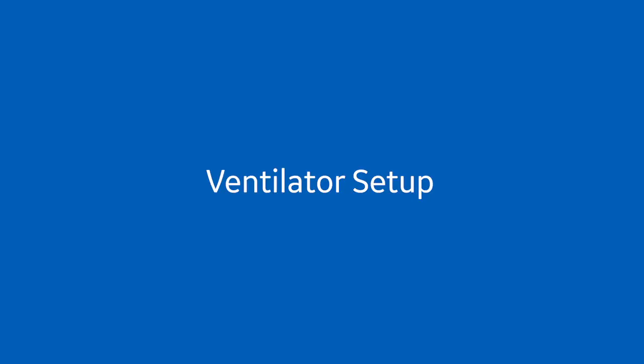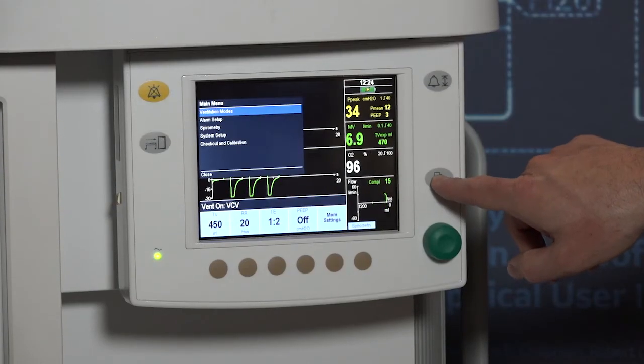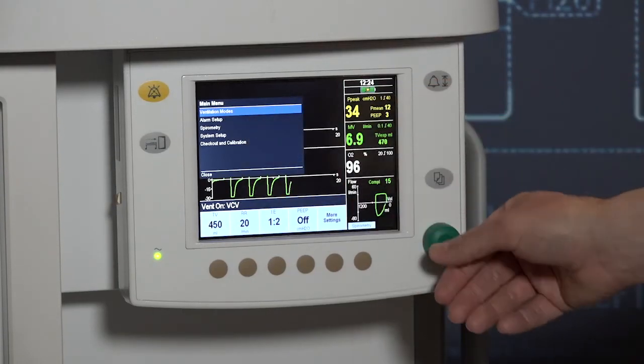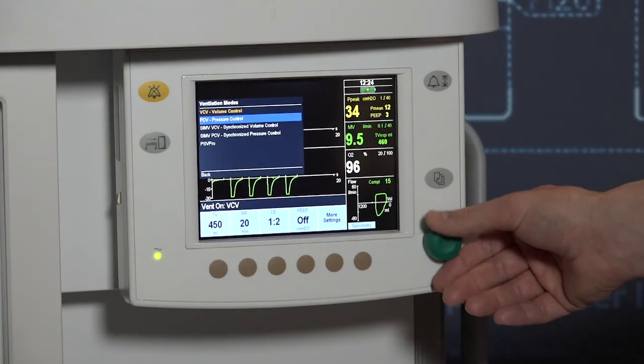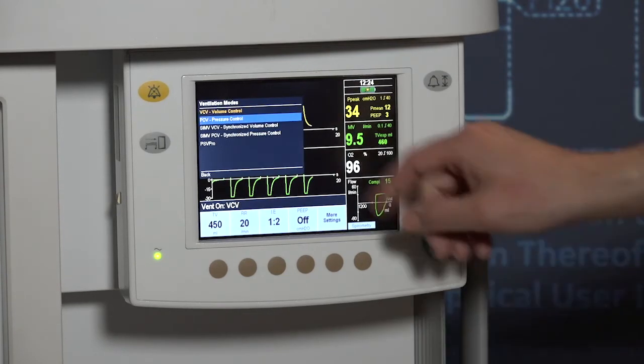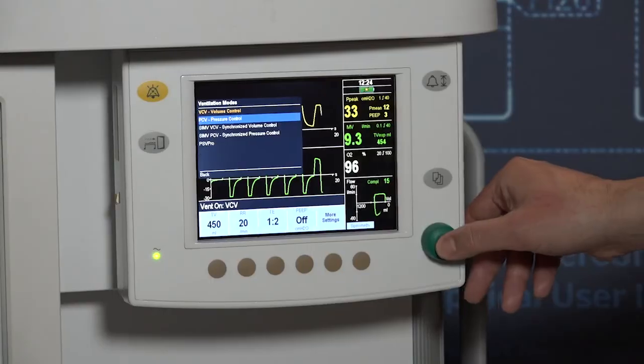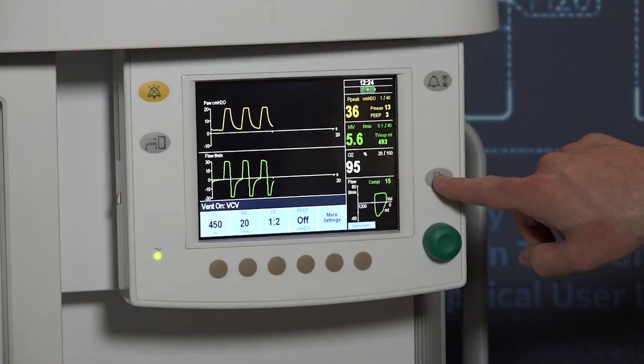To change the vent mode, select the menu key and select ventilation modes by pressing in the comm wheel. Select the desired ventilation mode. Set the tidal volume or inspiratory pressure using the comm wheel and confirm by pressing the hard key or by pressing in the comm wheel.